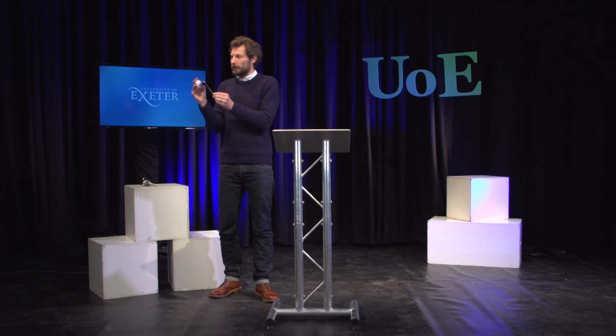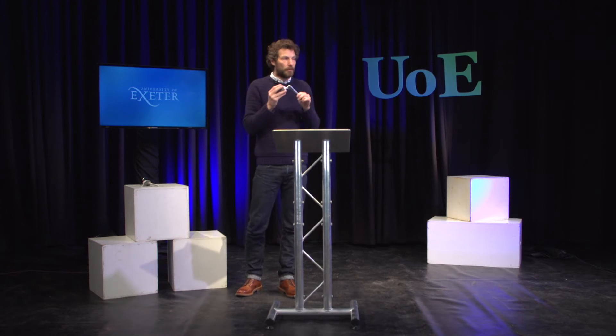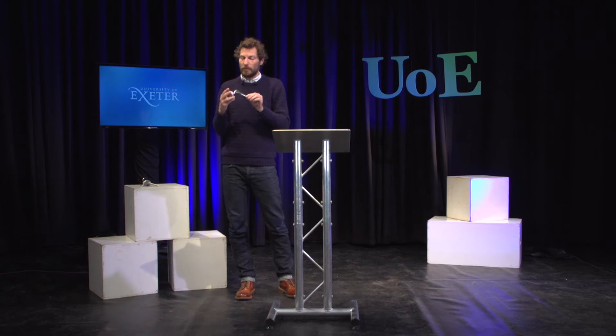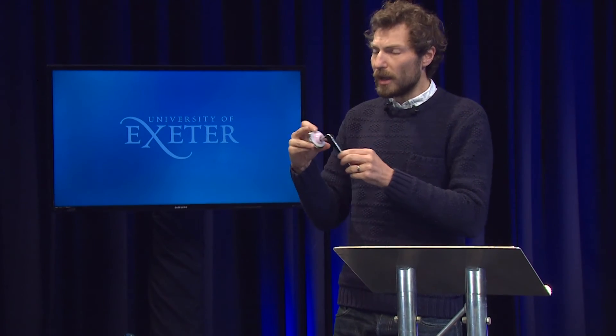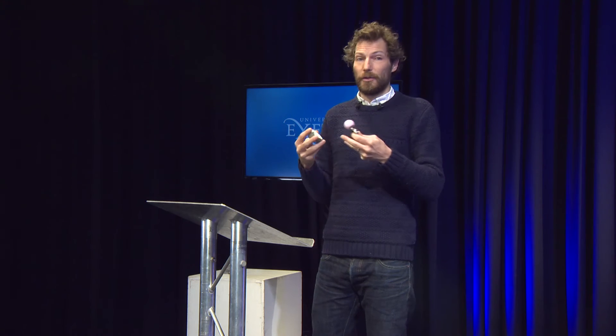And the reason you have a ceramic head and a polyethylene liner is so that the coefficient of friction between these articulating surfaces is very low, and that reduces the wear that occurs during those high number of cycles that the hip will have to go through. These kinds of components are used in many hip replacements and it's an incredibly successful procedure. So after about 10 years, only about 5% would need revising, but about 100,000 are carried out in the UK every year, and so even a small improvement in performance can have a positive effect on thousands of patients.